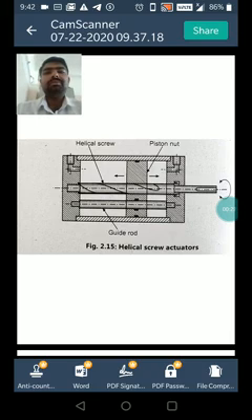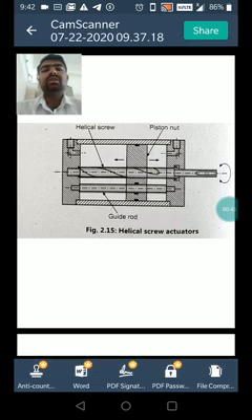This piston and the piston rod have helical grooves or splines and are meshed together like a nut and screw. As the piston is actuated under the hydraulic thrust due to the oil pressure, it causes the piston rod to rotate in one direction. The reversal of piston travel alters the direction of rotation of the rod.